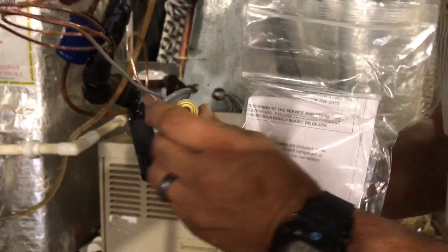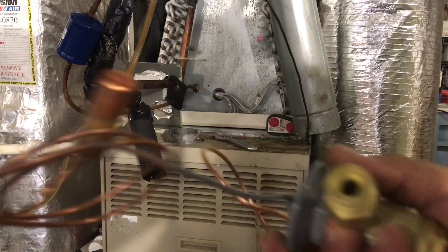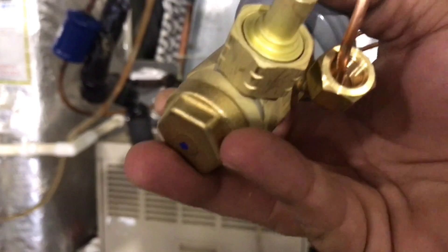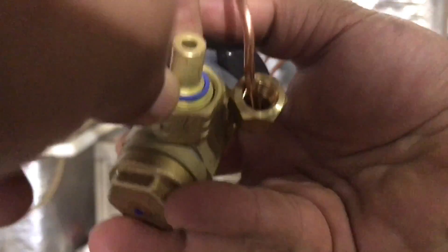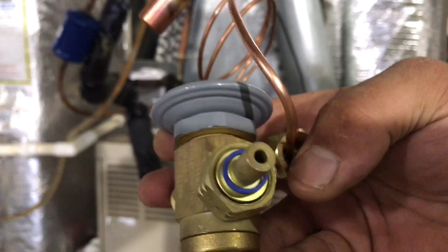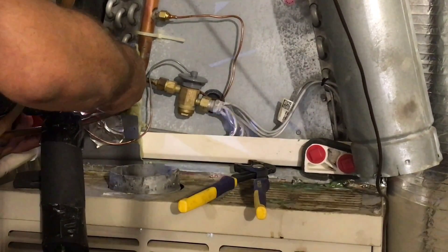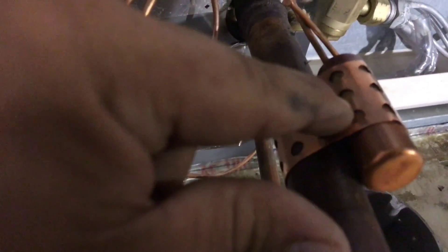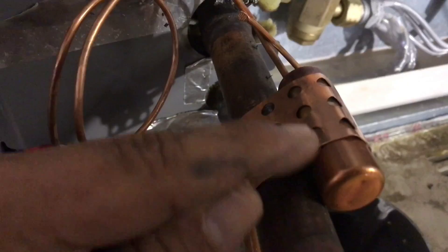In the pack you're going to have these little blue washers and you want to put them in right here. Set that in place like that, and then on this side - just like that. Make sure this thing is pretty tight on there. We've got our bulb on nice and secure at about 2 o'clock. You want to make sure that the hole underneath is touching your line - it doesn't need to have a gap in the middle where the line is bending. Make sure you're on a flat piece where it's touching all the way across.